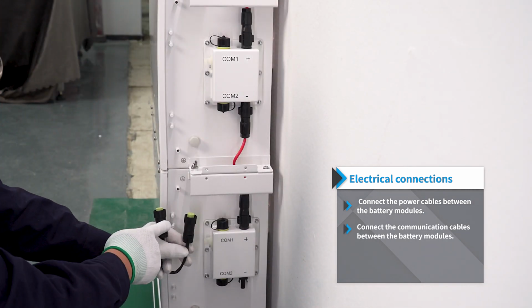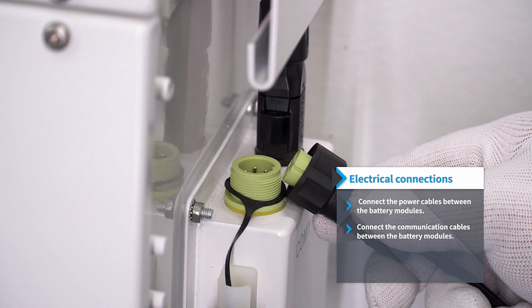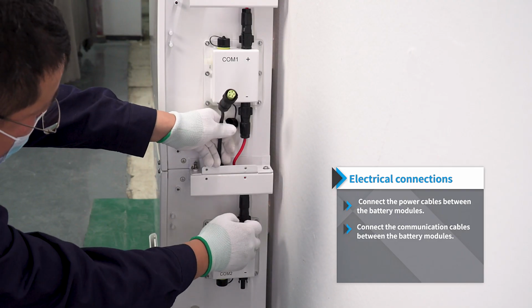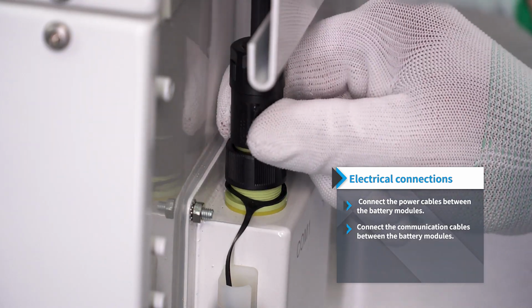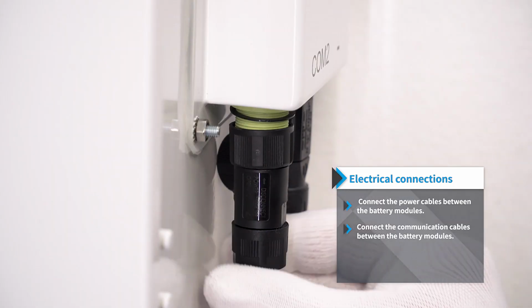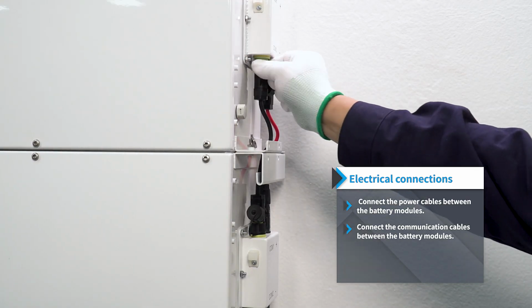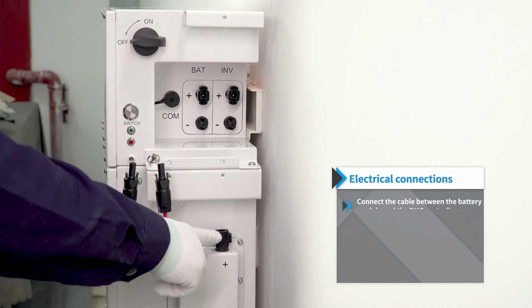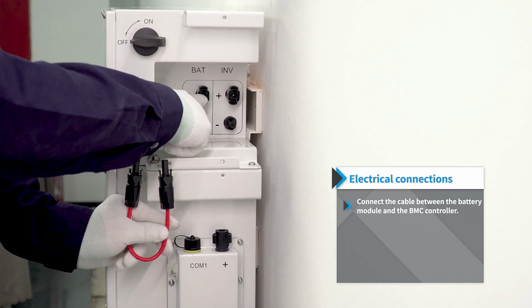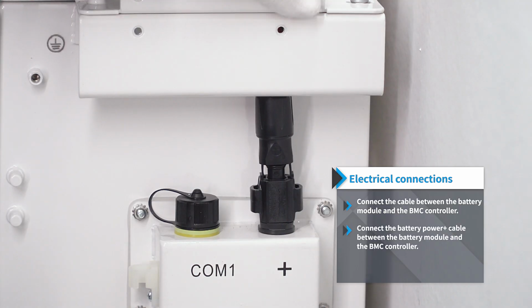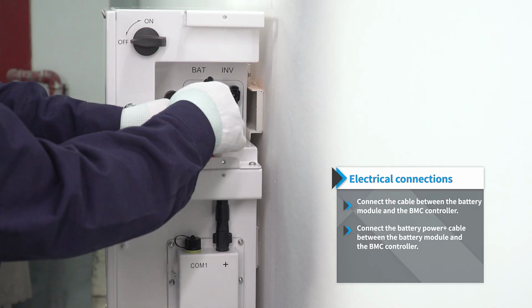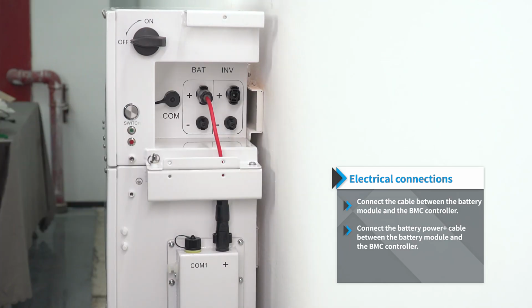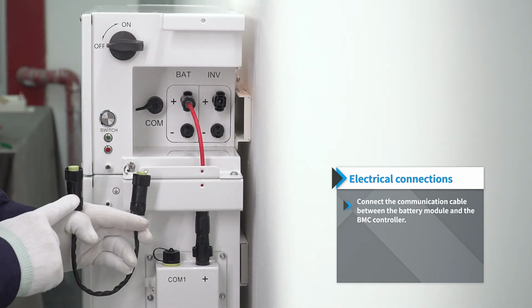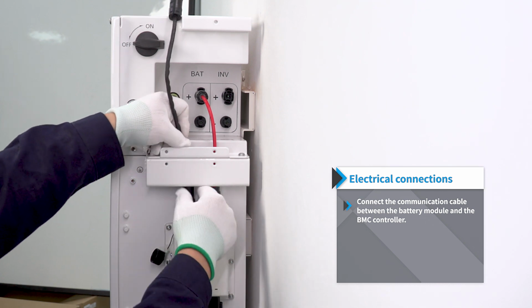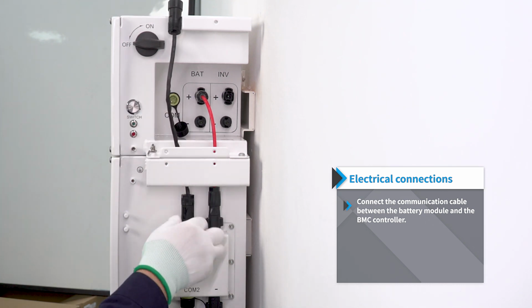Connect the communication cables between the battery modules. Connect the cable between the battery module and the BMC controller. Connect the battery power positive cable between the battery module and the BMC controller. Connect the communication cable between the battery module and the BMC controller.